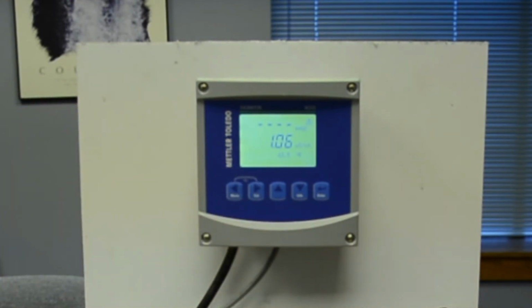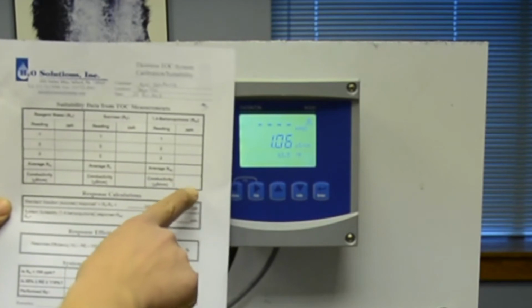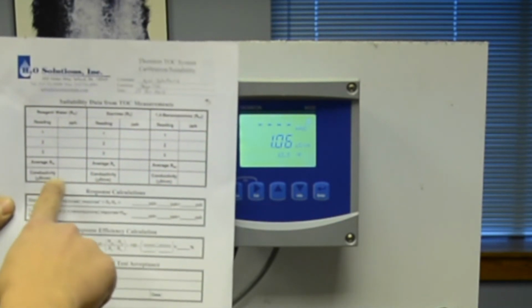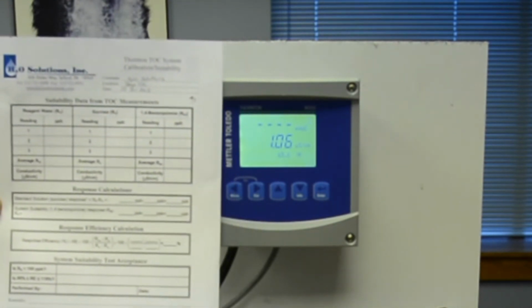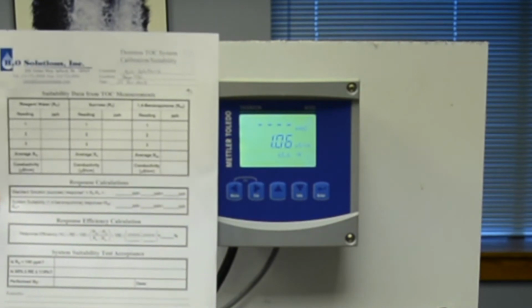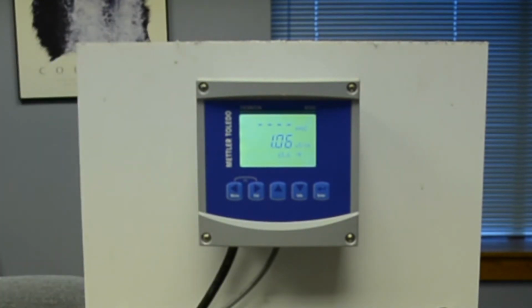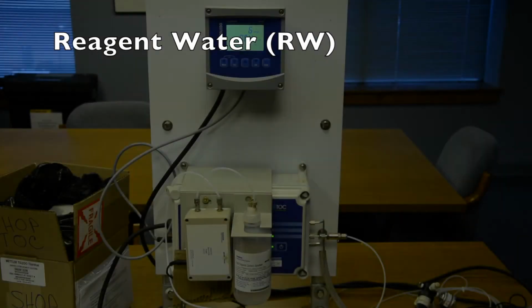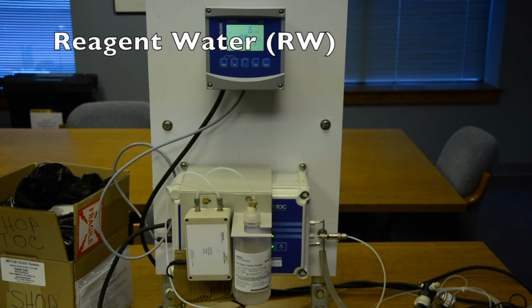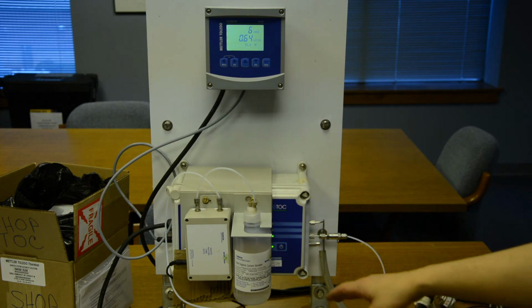The reason we need to do this is because on the suitability sheet, the calibration sheet, you will see that we need to write down what the conductivity is for each of the standard solutions that we're using. So now we're going to start off with the reagent water. I'm going to connect that up, and I'm going to start our pump, and we're going to see what it's reading. Be sure to readjust your flows after installing any new solutions.